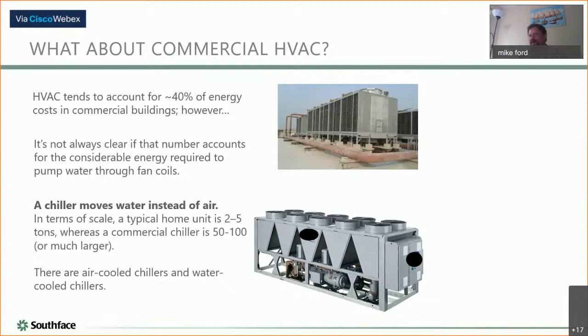Another note - if you have a big building, you may need water-cooled chillers, and you also have cooling towers, which are another way to remove heat from the space. We try to recommend against them when possible, and we also recommend against water-cooled chillers. There may be some efficiency advantages there, but they're really for highly qualified maintenance people - they require a lot of maintenance. And if you don't maintain them well, you can get real health hazards like Legionnaire's disease.